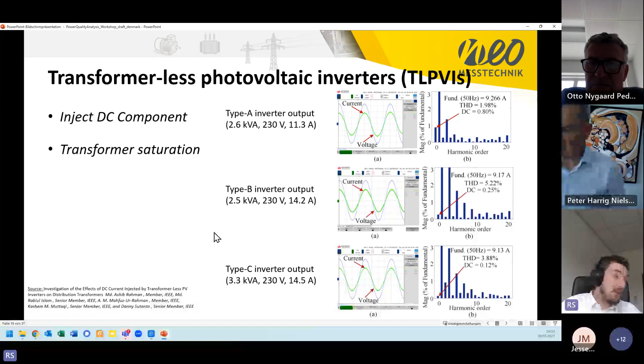The second effect, which is maybe starting to get more important in northern Germany, or in the northern countries where it's already known, because in Finland measurements were done a long time ago: we also see geomagnetically induced currents in the grid. During a geomagnetic storm, for example, we get a geomagnetically induced current in our grid, and therefore also DC currents at our transformer stations, putting them into saturation, and we get lifetime reduction.